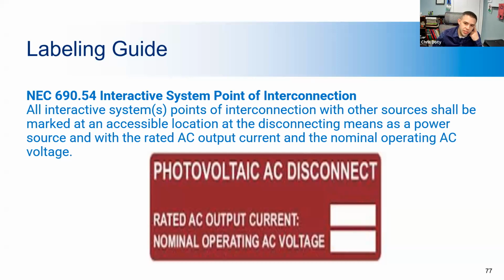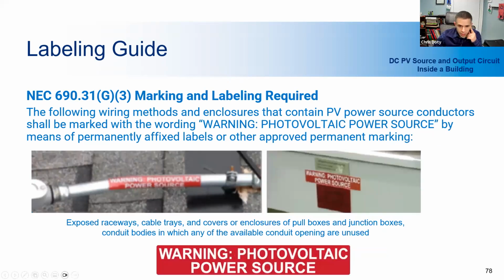Something to keep in mind is NYSERDA does not allow writing in on these labels. You want to have it engraved or printed onto the label. Engraved would be on a plaque or something, and printed would be on this kind of label. That's because over time, these systems are typically in the elements, or even if they're not, the writing will fade, and the information will basically disappear by the end of the system life. And so 25 years from now, no one will have a clue what was written here. So you want to definitely make sure it's engraved or printed.